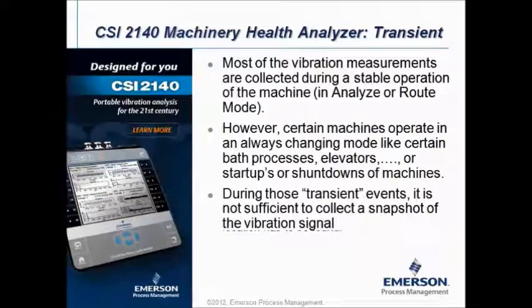Module number 4, transient. Most of the vibration measurements are collected during a stable operation of the machine in the analyze or in the route mode. So you measure the vibration signal on an installation for a short period, and after all, it doesn't matter if you take the short vibration measurement, the snapshot now or 10 minutes later or an hour later or a day later, the machine is running in a stable condition and you want to measure a short snapshot.